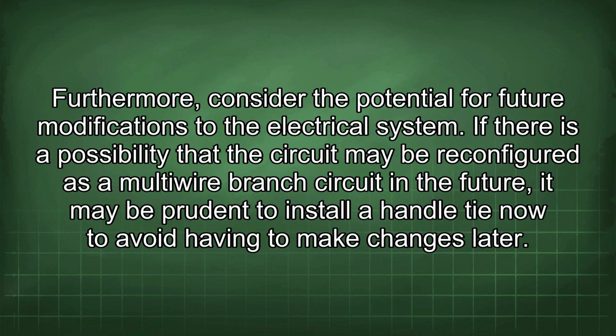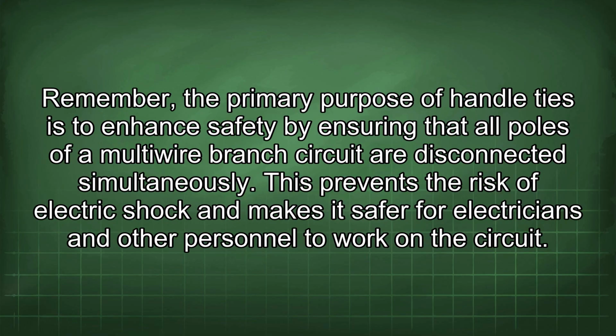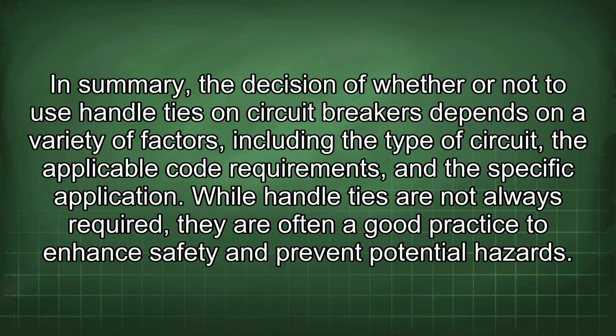Furthermore, consider the potential for future modifications to the electrical system. If there is a possibility that the circuit may be reconfigured as a multi-wire branch circuit in the future, it may be prudent to install a handle tie now to avoid having to make changes later. Remember, the primary purpose of handle ties is to enhance safety by ensuring that all poles of a multi-wire branch circuit are disconnected simultaneously. This prevents the risk of electric shock and makes it safer for electricians and other personnel to work on the circuit. In summary, the decision of whether or not to use handle ties on circuit breakers depends on a variety of factors, including the type of circuit, the applicable code requirements, and the specific application.